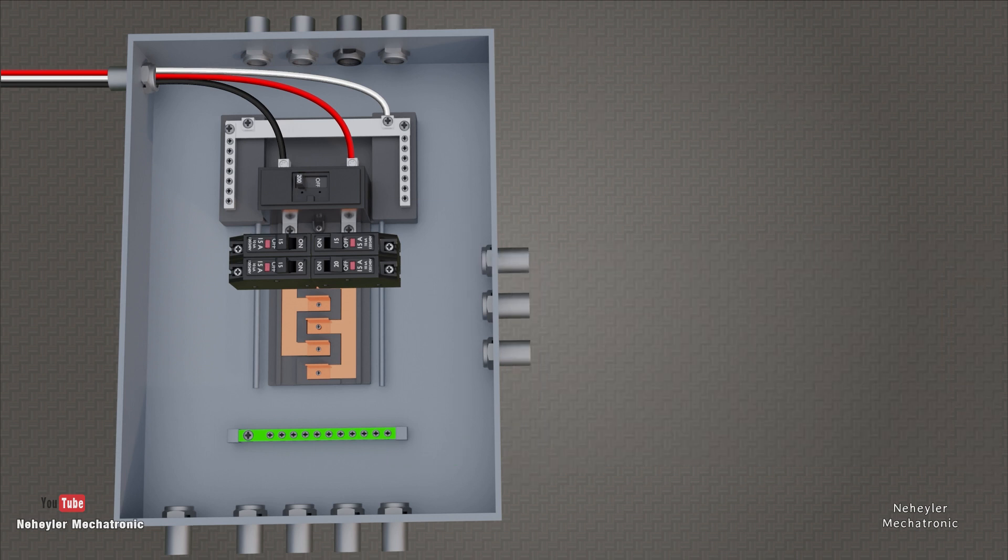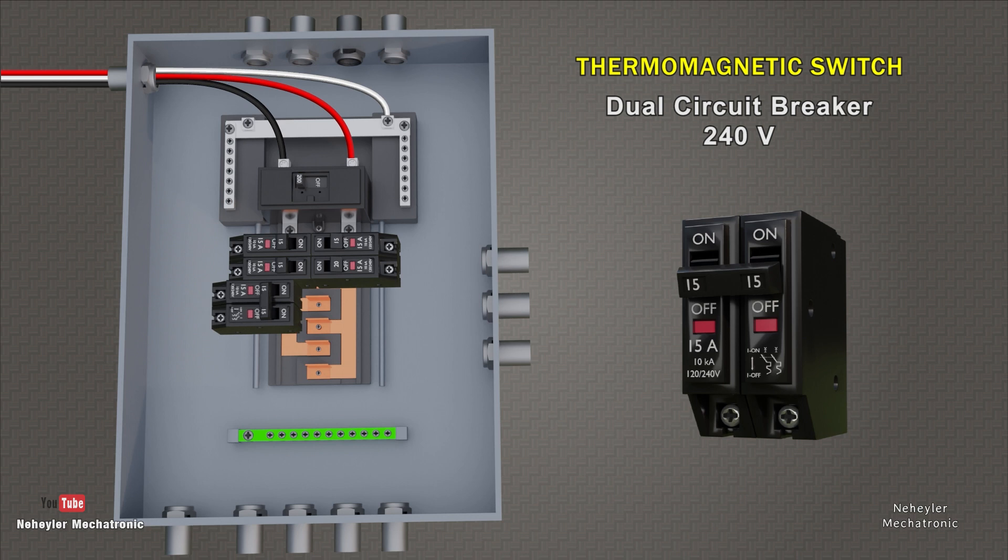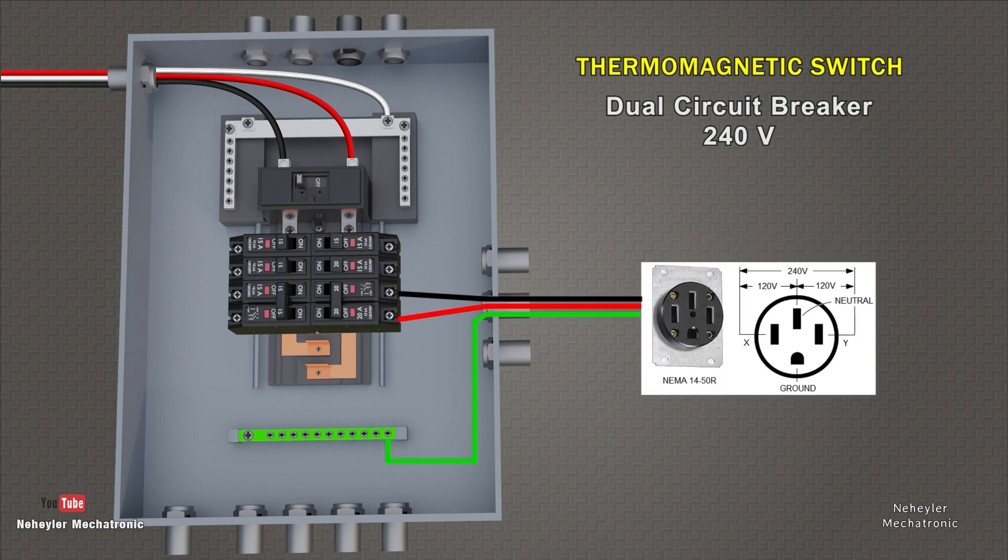It is also possible to consider bipolar or dual breakers. This element is usually used when you have machines that require a voltage of 230 or 240 volts, such as motors, air conditioning, stoves, etc. These can be 15, 20, or more amperage. The connection is made using the two hotline wires and the ground wire. In some cases, the outlets also have a terminal for connecting the neutral wire.